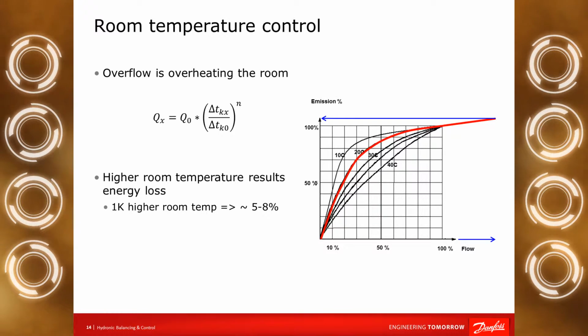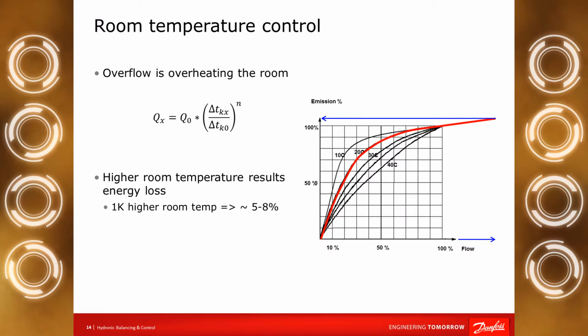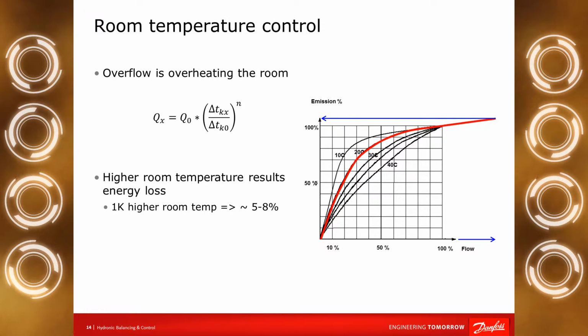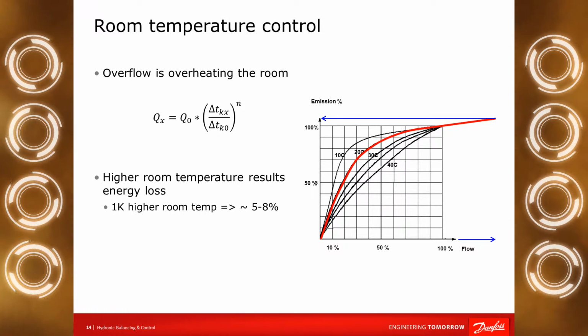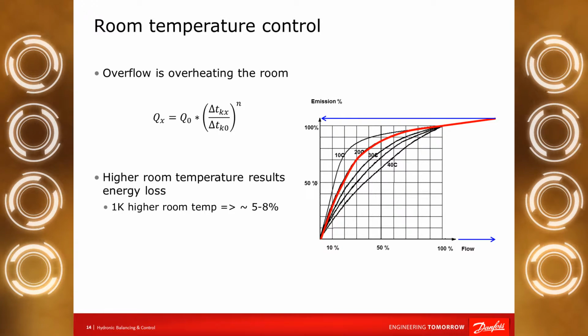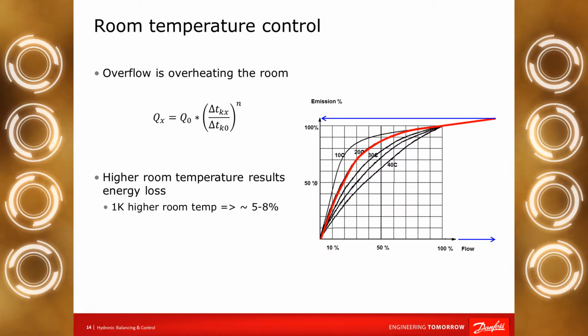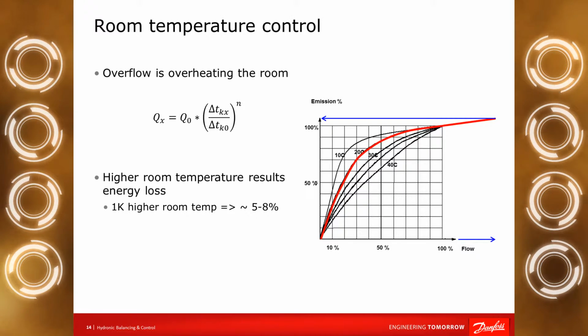And the last one, but not least, we have to mention the overflow effect on the room temperature control. If we have overflow in the system, we have higher room temperature oscillation, because this overflow will ensure more emission of the heating radiators. In this case, the system will be overheated, and the window will most often be opened and the energy leaves through the window.